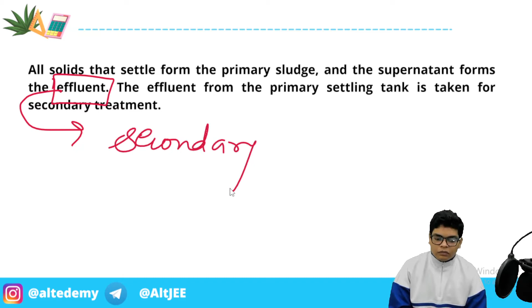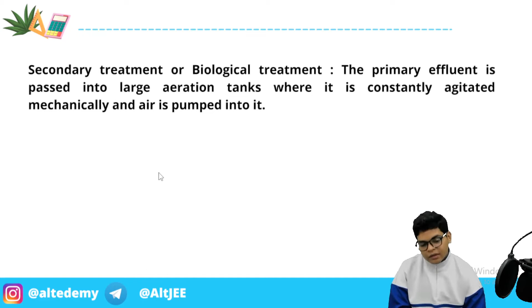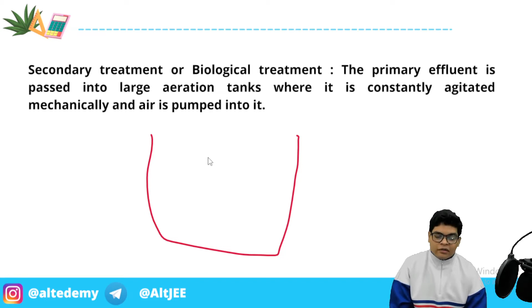Now what happens? In secondary treatment, or biological treatment, the primary effluent is passed into large aeration tanks where it is constantly agitated mechanically and air is pumped into it. These are very big tanks, and they contain large amounts of air, oxygen. There is constant agitation. What is agitation? That is continuous mixing of the primary sludge with high intensity. Why do we have to mix it? So that it mixes with the air which is pumped into the tanks.